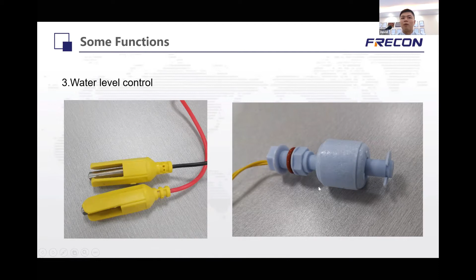The third function I'm going to introduce is water level control. In this function, you need to add a water sensor. For example, if you have a tank, you install this sensor in the tank, and once the water is full, it will tell the inverter to stop the pump. Another application is you install the sensor in your well; if the well runs out of water, it will also tell the inverter to stop running.